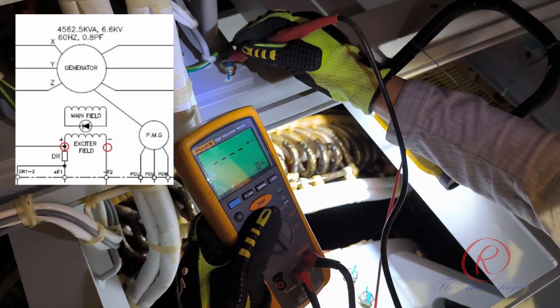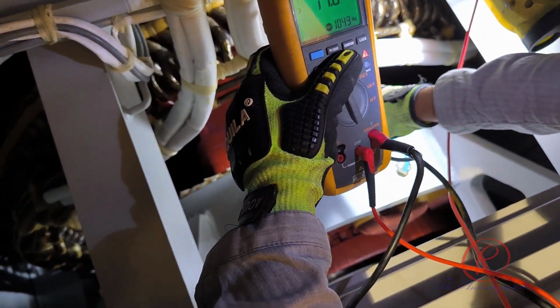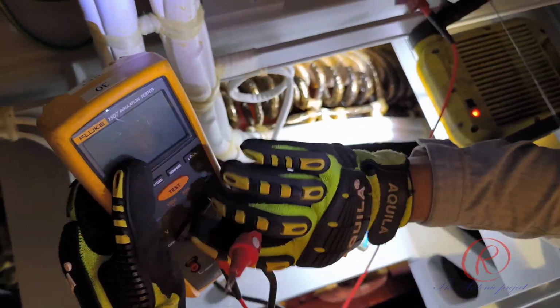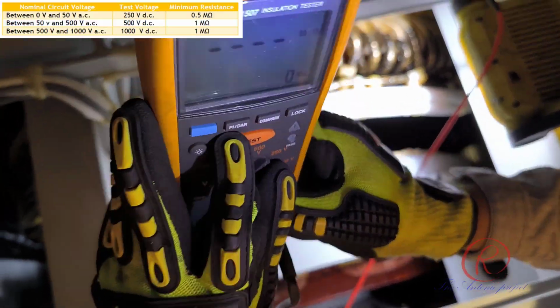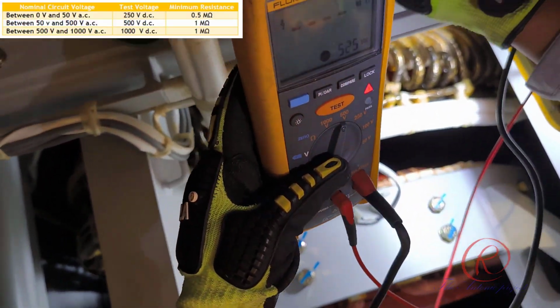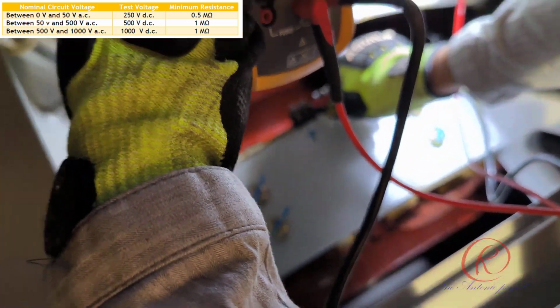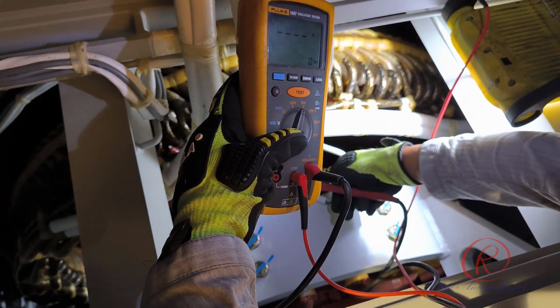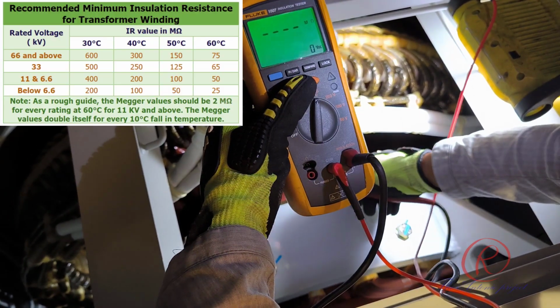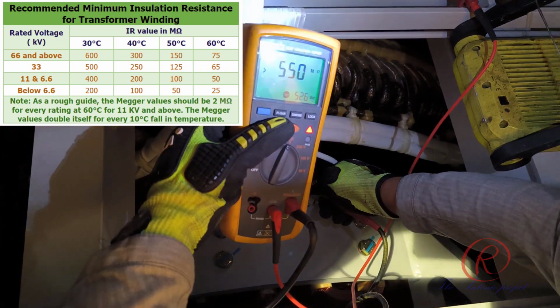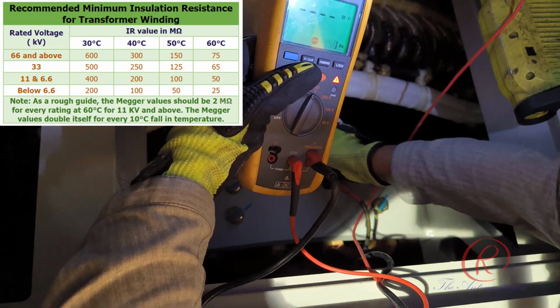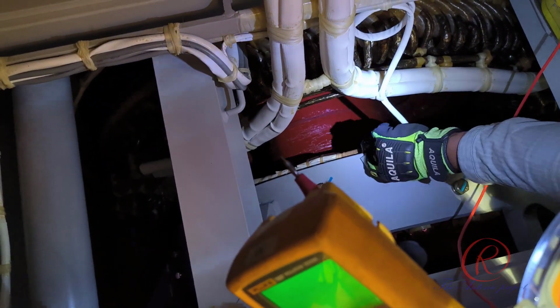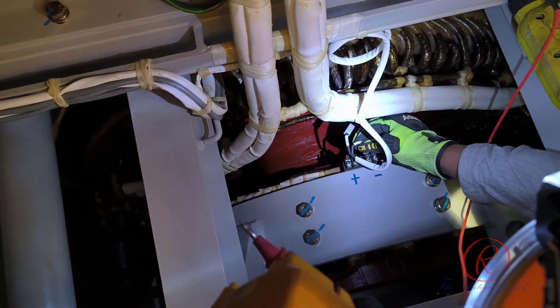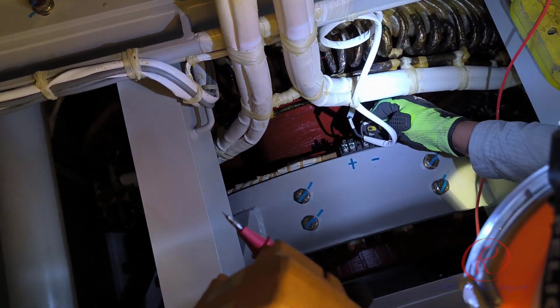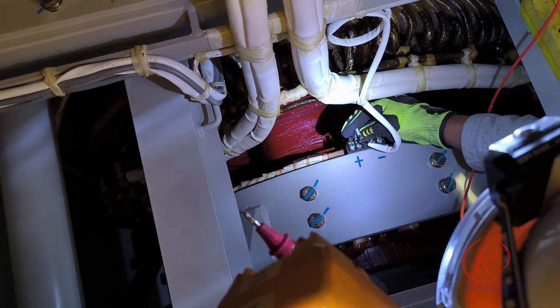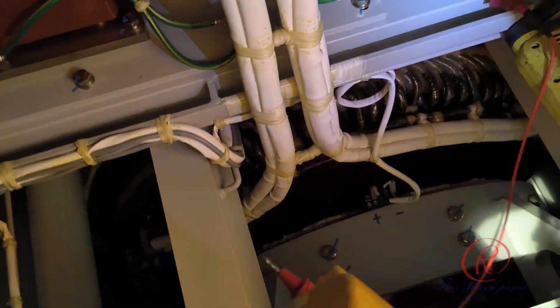For exciter insulation resistance measurement, the test voltage used is 500 volt DC. Fluke 1507 is suitable for this work. Confirm that insulation resistance of the exciter is under normal condition. It is considered that all windings insulation are in good condition. Humidity is under normal condition too.